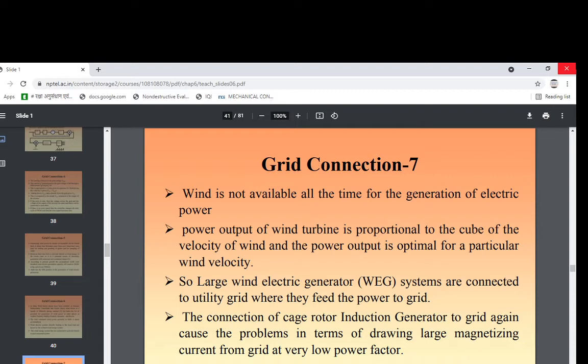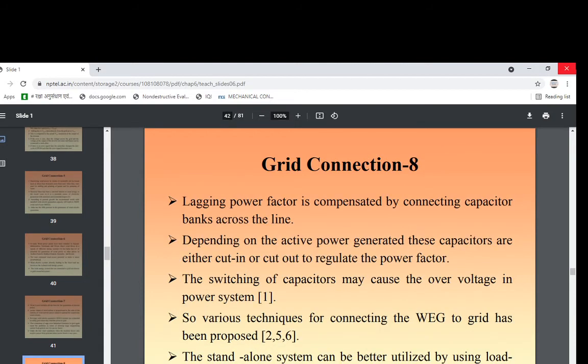Under low wind conditions, the machine draws only reactive power from the grid and the power factor is very poor. Lagging power factor is compensated by connecting a capacitor bank. Depending on the active power generated, these capacitors are either cut in or cut out to regulate the power factor. The switching of capacitors may cause overvoltage in the power system, so various techniques for connecting the WEG to the grid have been proposed. The standalone system can be better utilized by using load matching techniques.